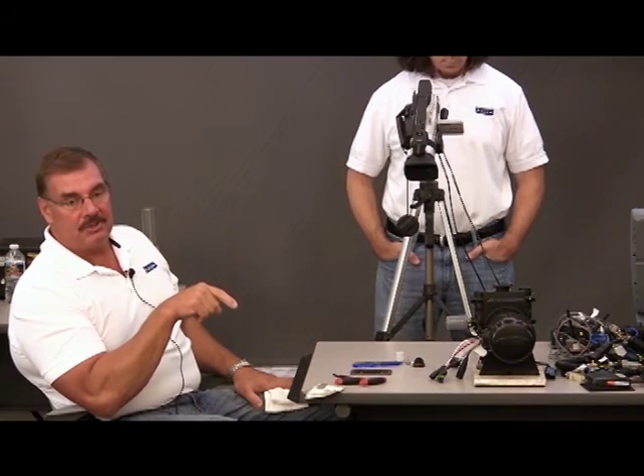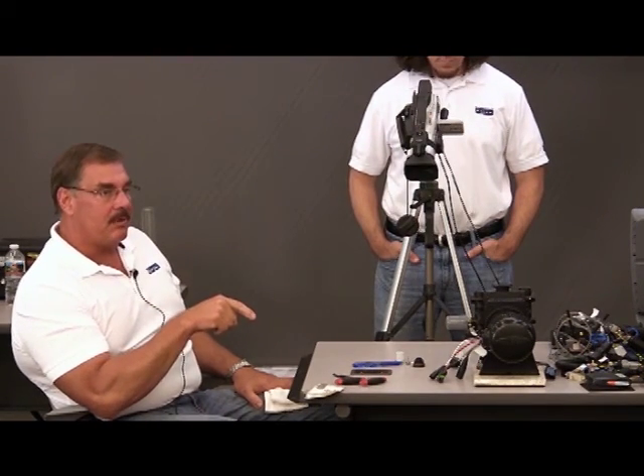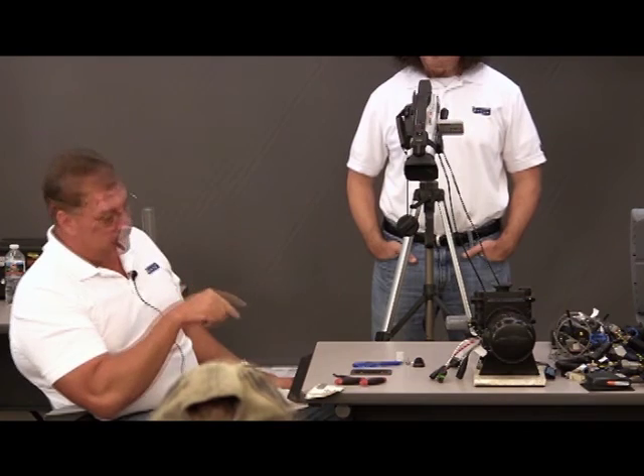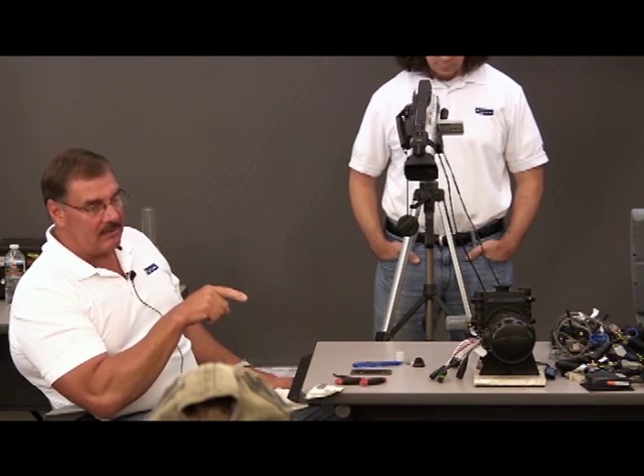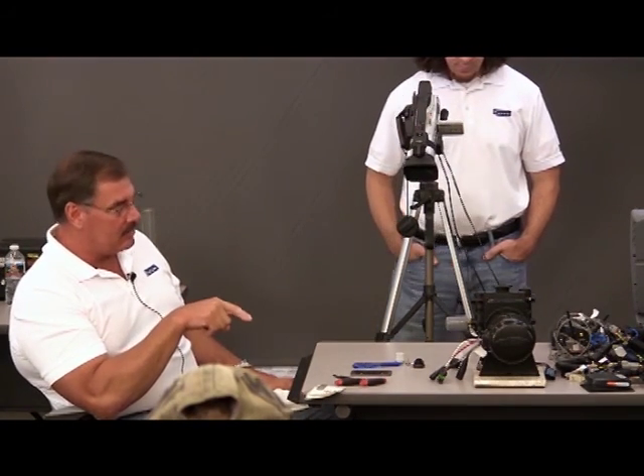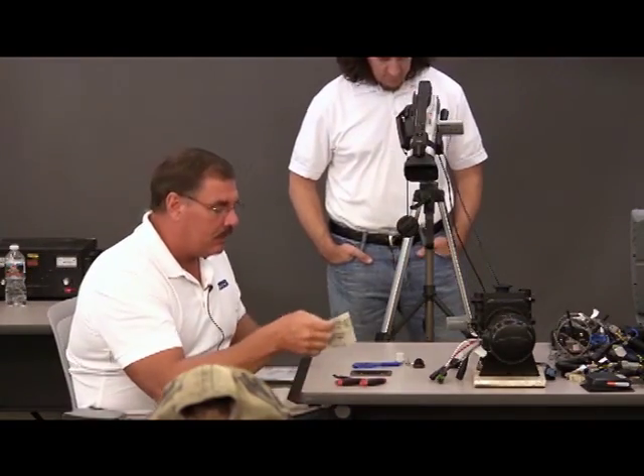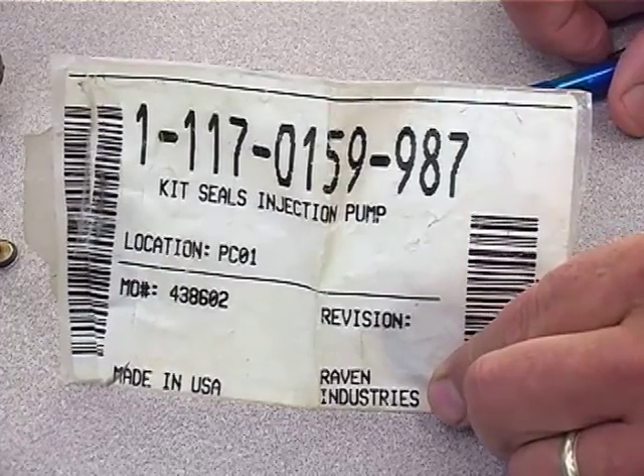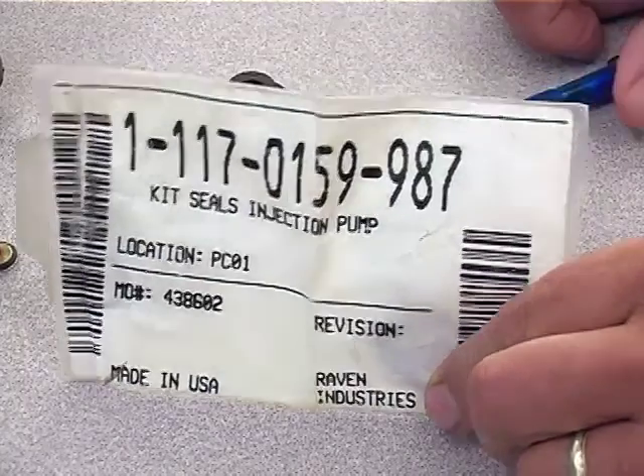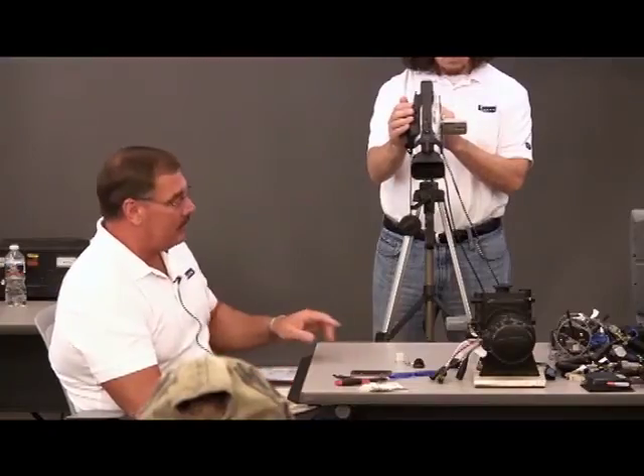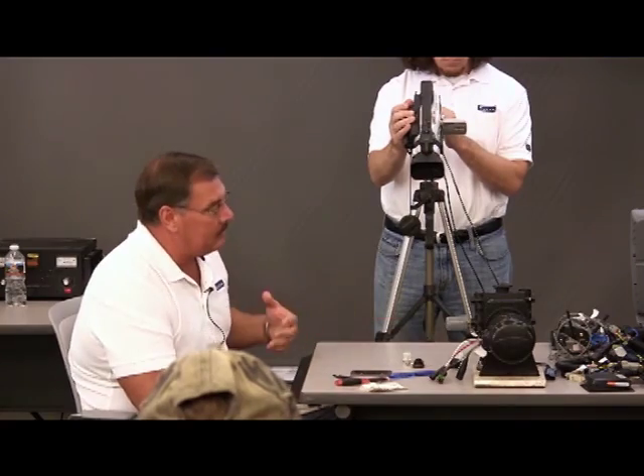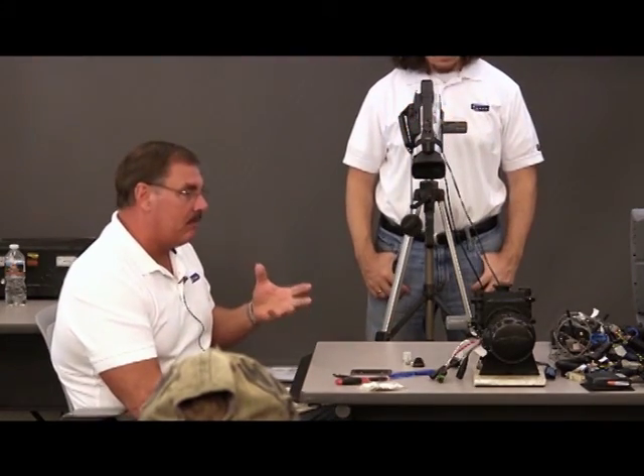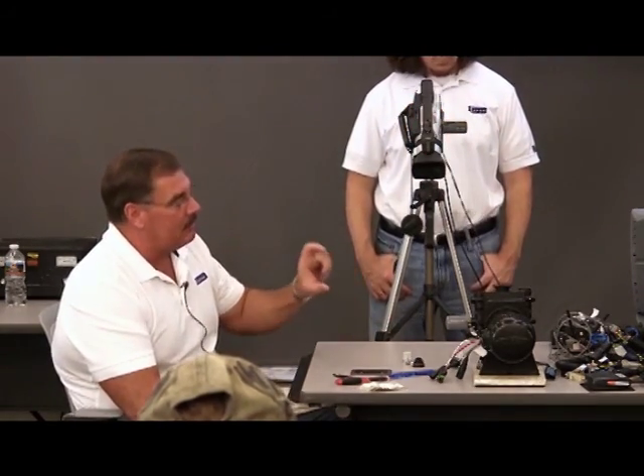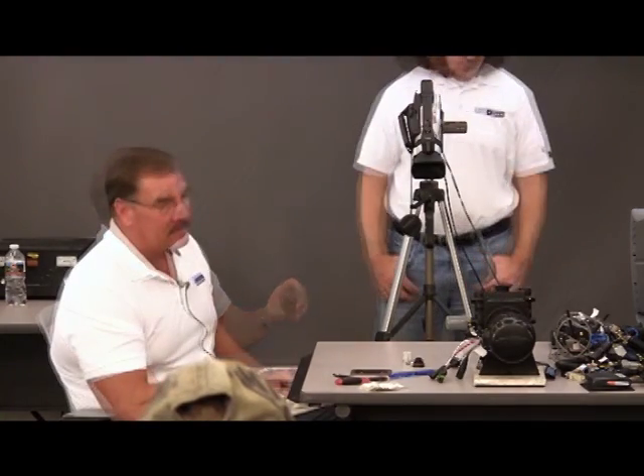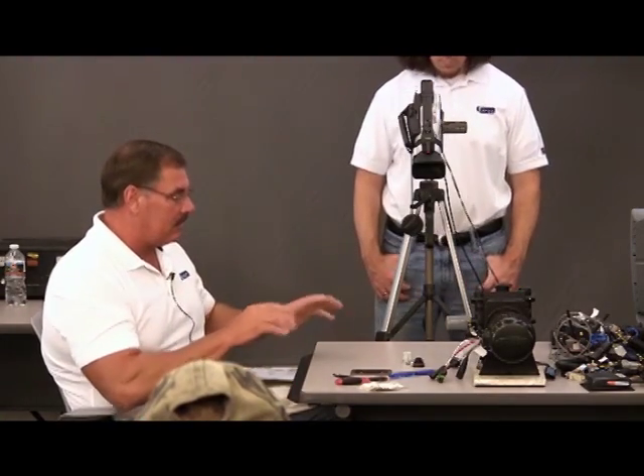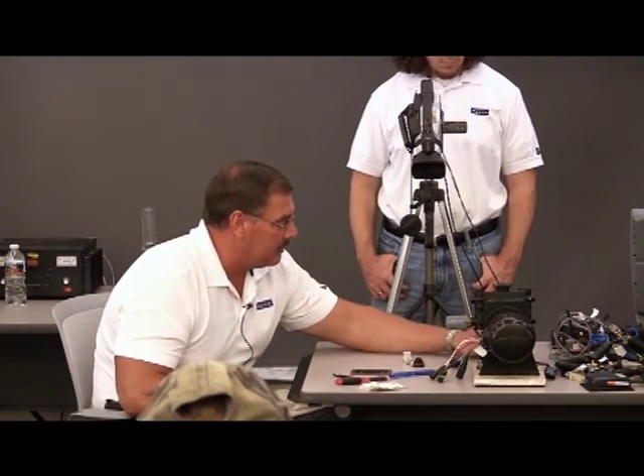Once you're ready to start your season, that's when we take the pump apart, go through those seals, and I would replace them all. If they've had N-Serve the year before, replace and put a whole new set of seals in. We have a seal kit that has all these parts in there, 117-0159-987. That would be our recommendation. I think a lot of times people are afraid to see all these moving parts. What can I do? If you break them down one piece at a time, it's not that tough. You just have to spread it out, keep everything together, and it works pretty good.